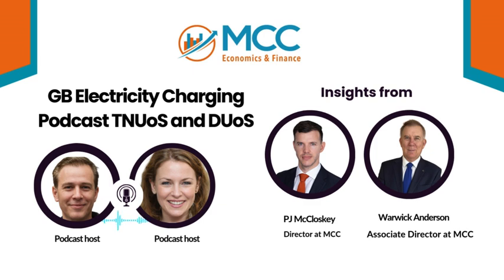TNUoS realized that intermittent generators' output goes up and down, so they set lower per kilowatt unit rates to compensate for that. So wind and solar get a lower rate because they're not always producing power. Exactly. Because their capacity factor is lower, they pay less per unit. So it's kind of like a volume discount because they're not as consistent? Yeah, you could think about it that way.